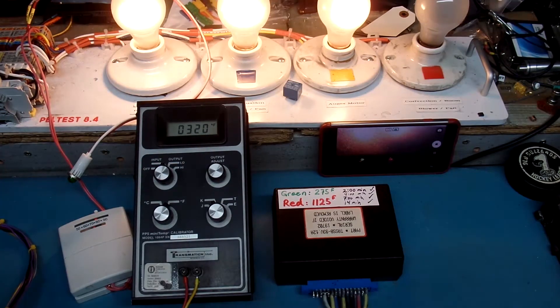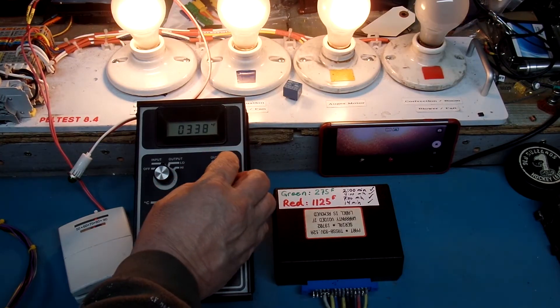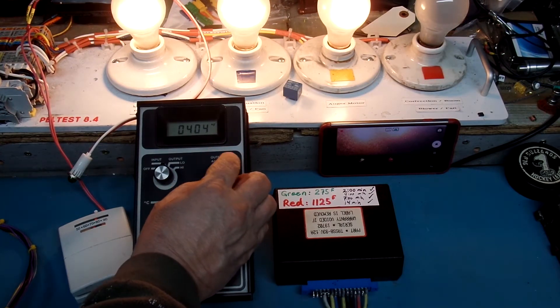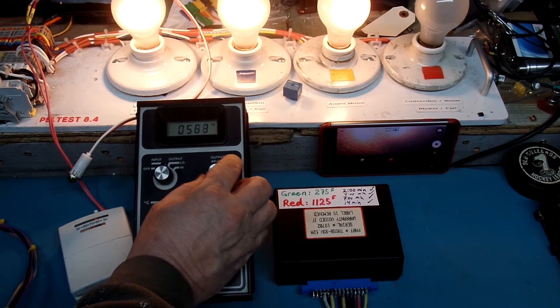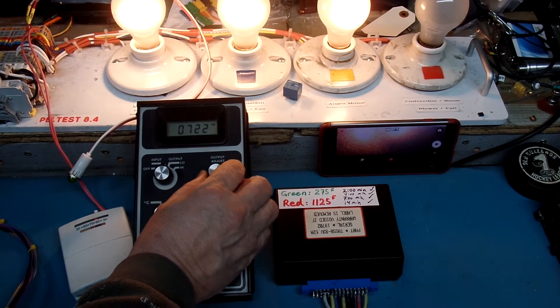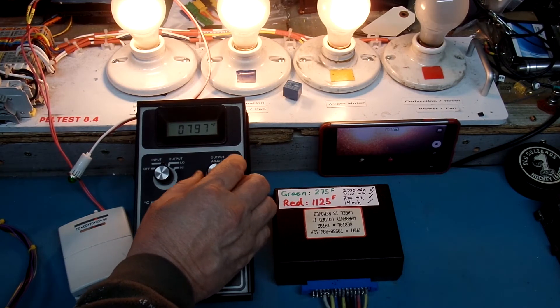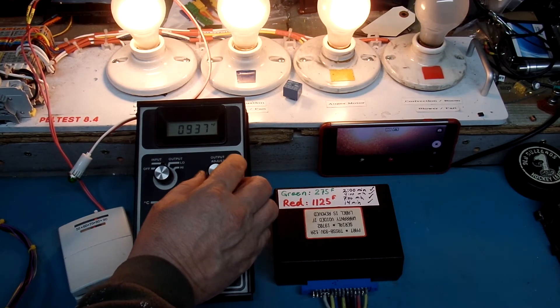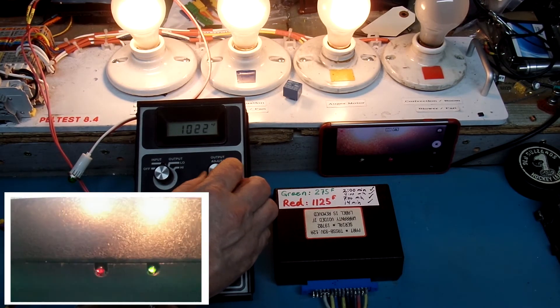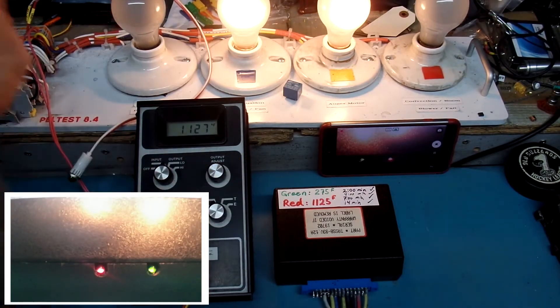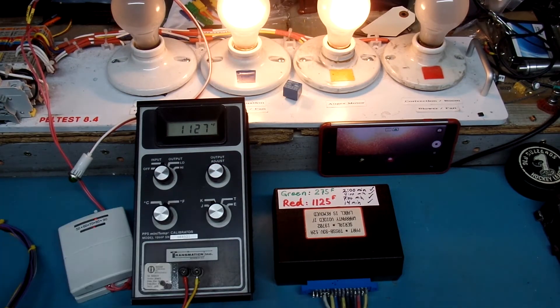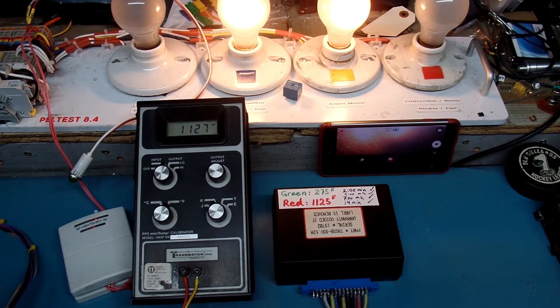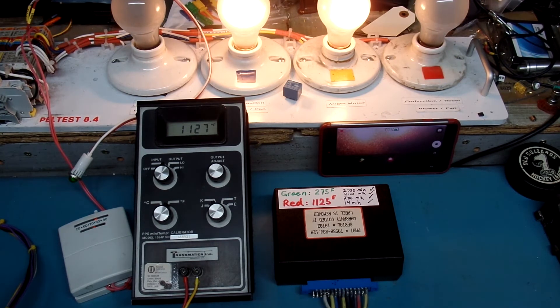Nothing has changed. If I increase the temperature up to 1125 degrees Fahrenheit, things will change. We'll see the red light come on and we see that the igniter has been shut off. That's basically saying that the temperature of the fire is hot enough. There's no need to be using electricity to keep the igniter going.